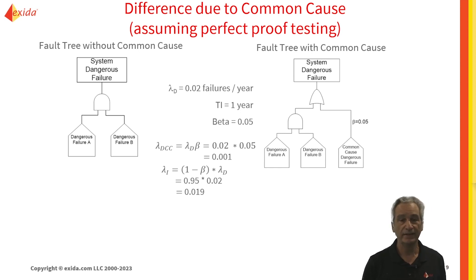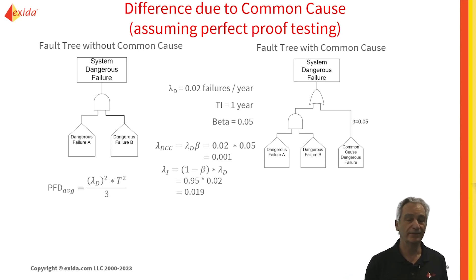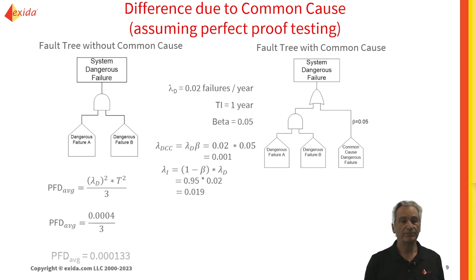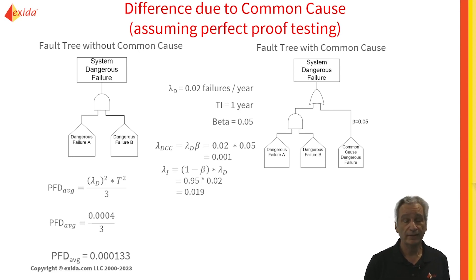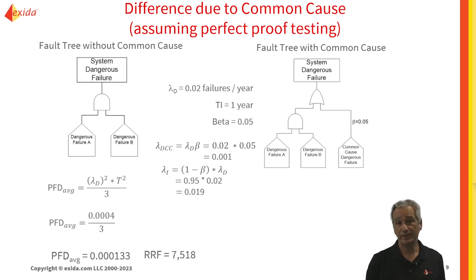Going back to the left-hand side of the fault tree — ignoring common cause — we know that to calculate the PFD average, it's going to be lambda_d squared times t squared over 3. If we plug in our numbers, we end up with a PFD average of 0.000133. The risk reduction factor is 1 over the PFD average, so dividing gives us a risk reduction factor of 7,500, which would tend to indicate this can achieve a fairly high SIL 3. Because we're not considering imperfect proof testing, these numbers will be much higher than they would otherwise be, but for comparison purposes that's fine.